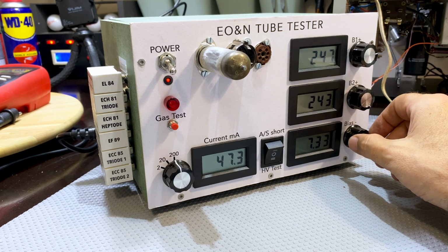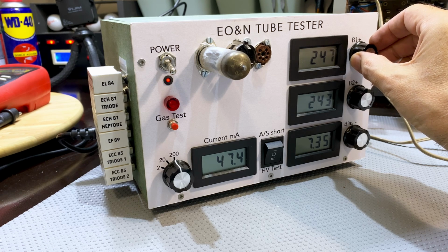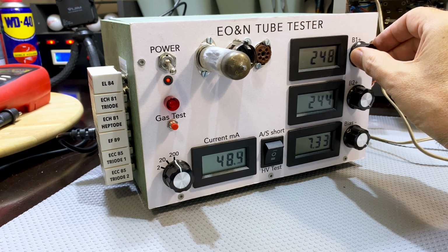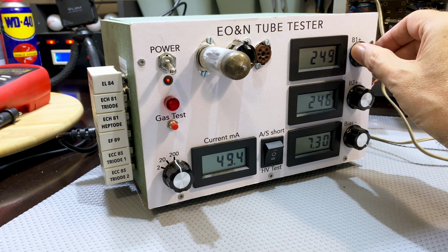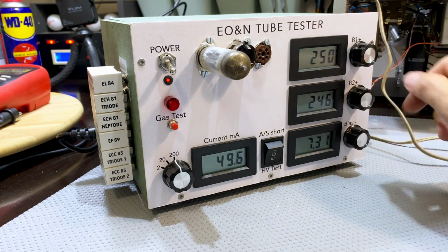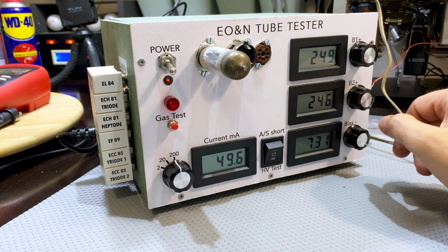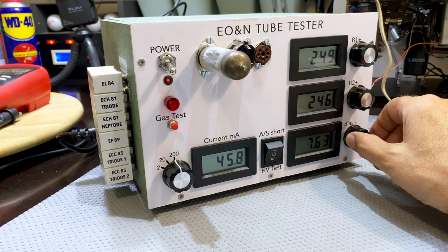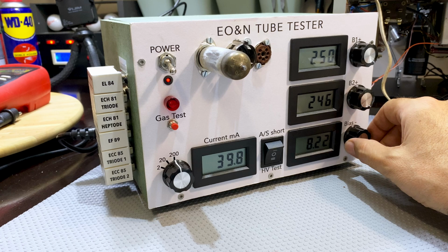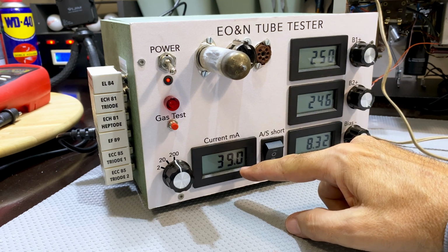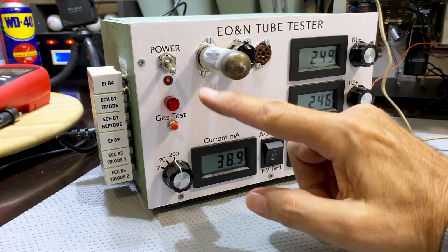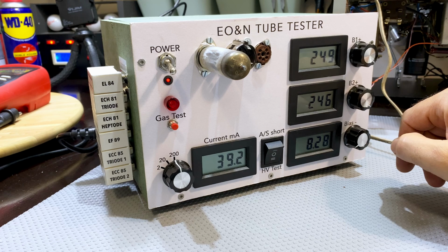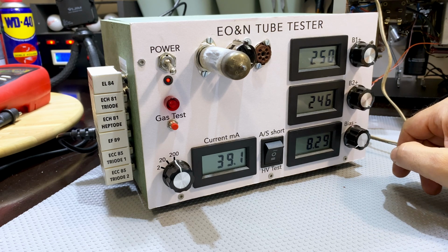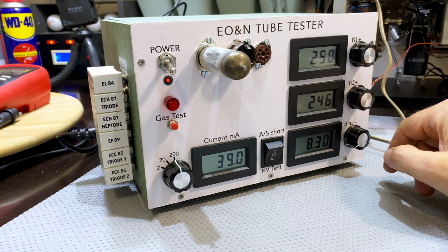Now if I go to minus 8.3, let me touch that up a little bit. I'm having a bit of a problem with those reference diodes, they fluctuate a little. So this thing is actually better than perfect. At 7.3 I get 49.6. If I go to 8.3, I get 39.0, so that's 10.6. The standard operating conditions say the S should be 11.3, so we're at 10.6 - that's very close.